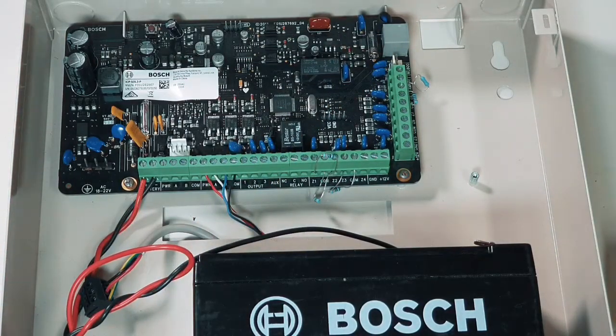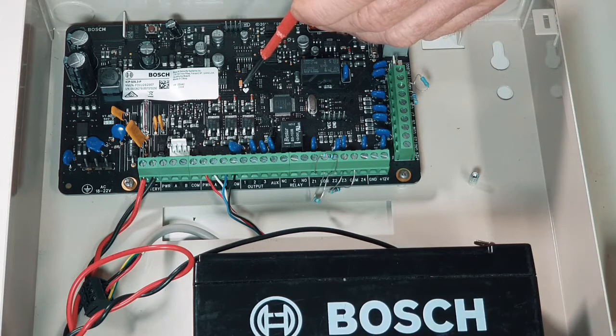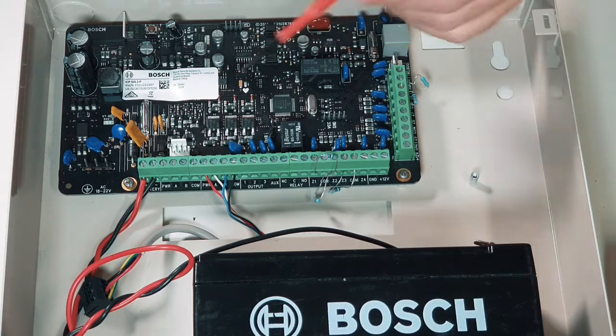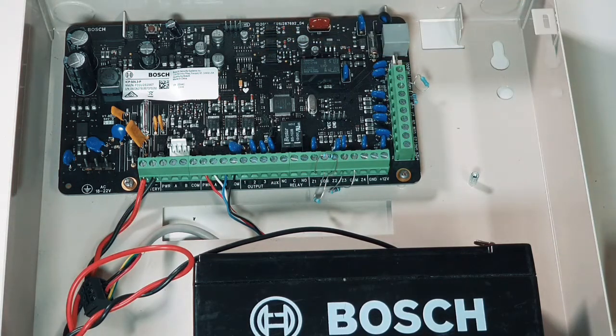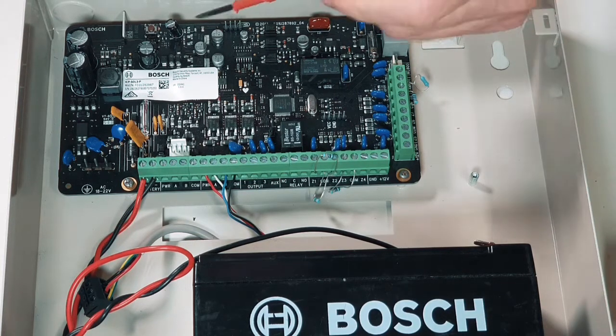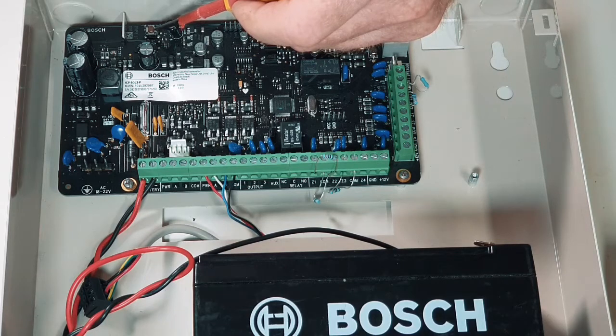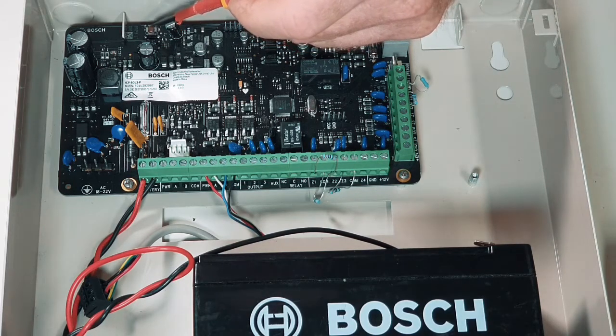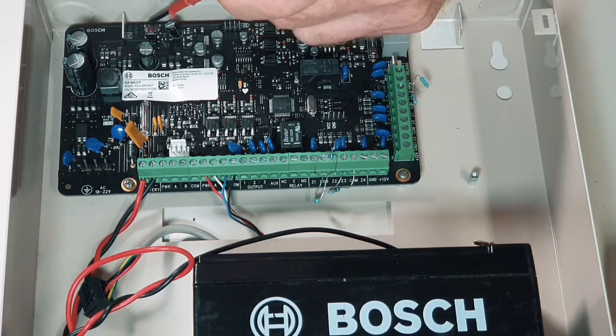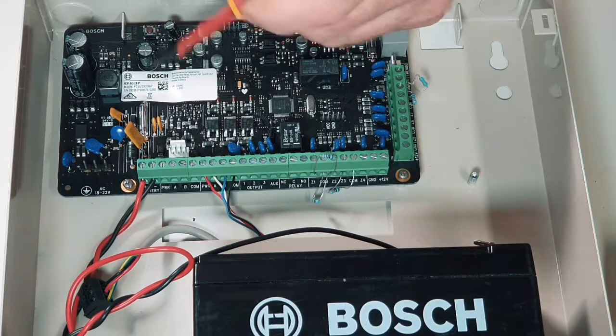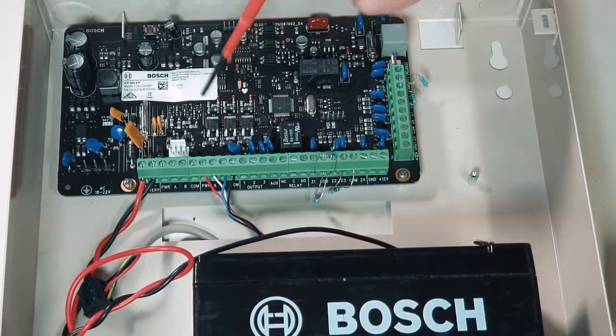If you noticed before, you may not have, there's a little red light that was on here when we had power on, this heartbeat light. That's now disappeared, so we know we've got no power on the system. To default the system, we need to press and hold this default button, and it's right here at the top of the board. It actually says default above it, so the word default is printed on top of the board here. This is actually a Solution 3000 board.